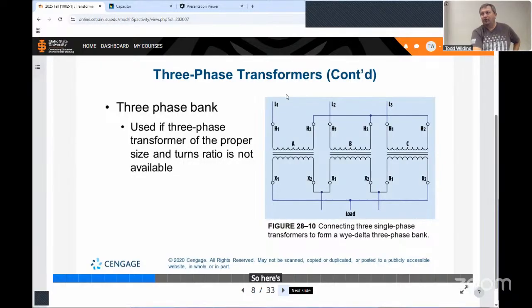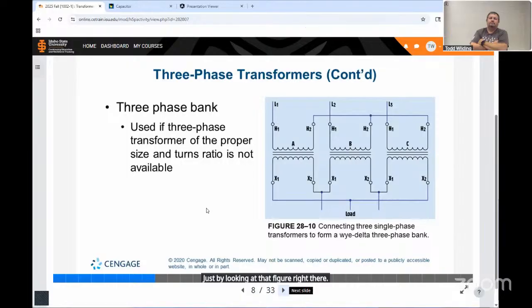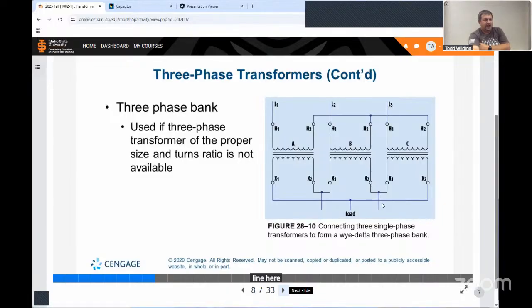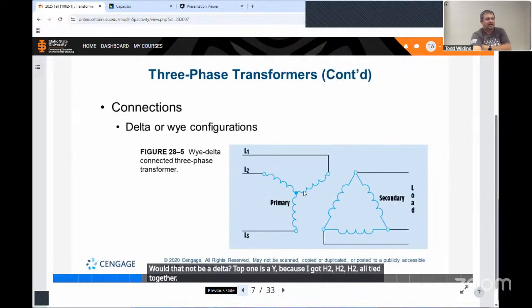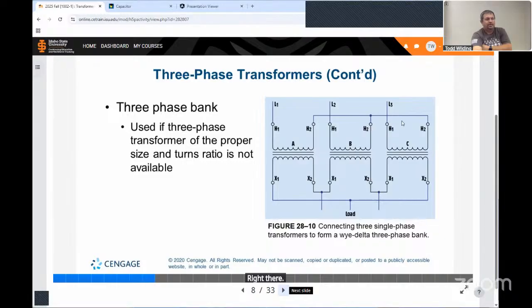So this is how I learned when I went through school to tie my transformers together. Can anybody tell me which one of those, top or bottom, is a delta connection? Just by looking at that figure right there. The bottom is a delta. Line here, and then that comes all the way around, ties into that one. Would that not be a delta? Top one is a Y because I got H2, H2, H2 all tied together. Right there. All three tie together in one point. Then I got L1, L2, L3.